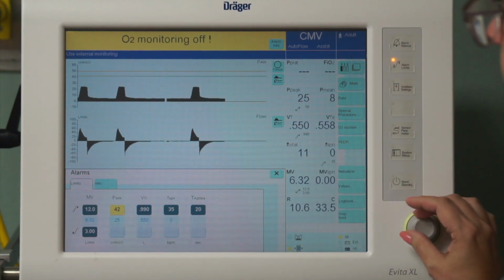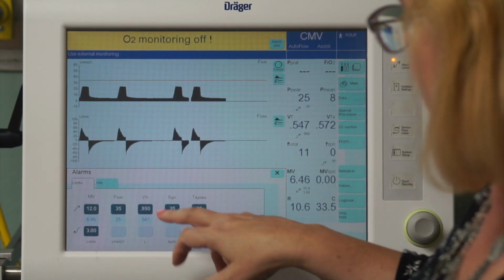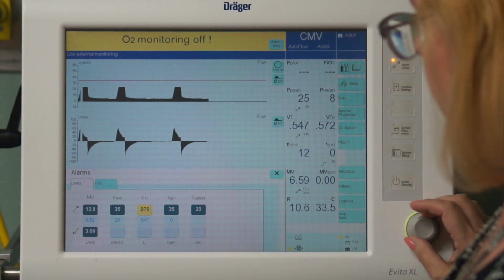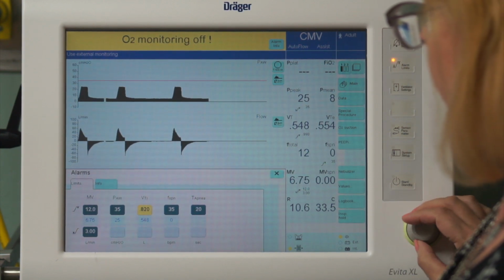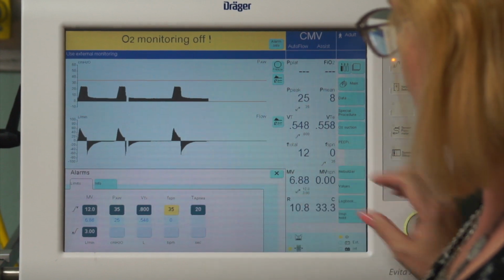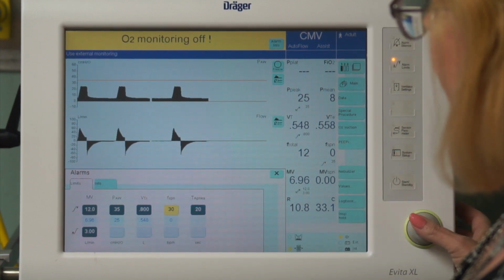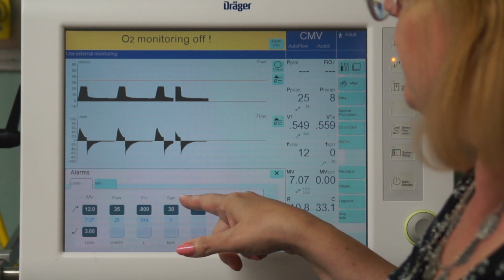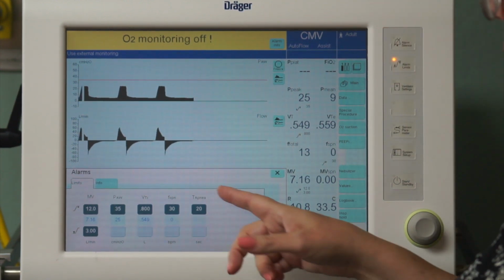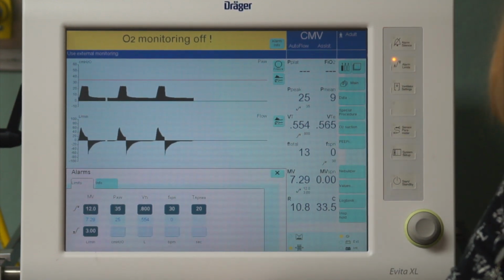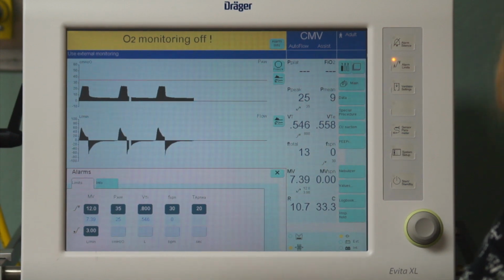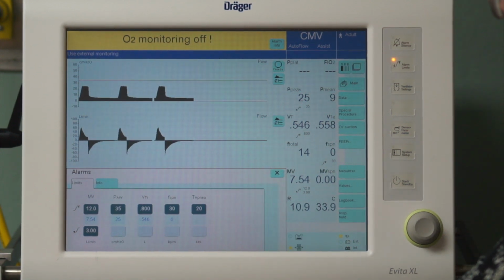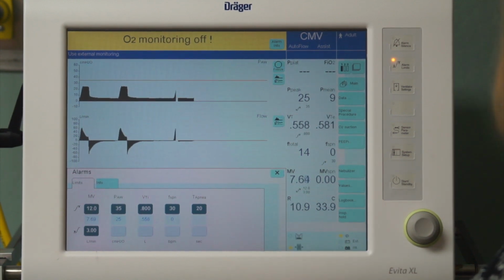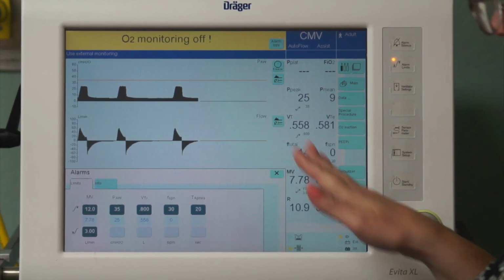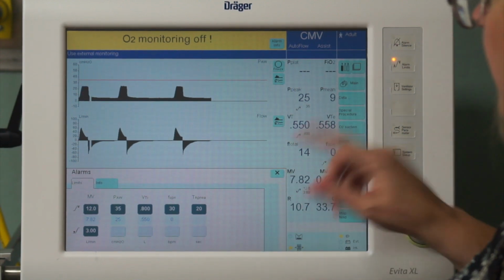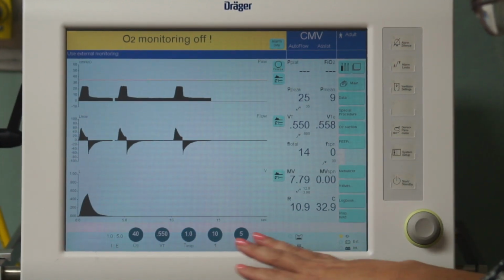Peak pressure, high of 50 seems a little excessive for this patient. High tidal volume. High respiratory rate. And notice what this says. This is a spontaneous respiratory rate. It's not a high machine respiratory rate, because if you think about it, that would be redundant, right? Because it's not going to be too high. So it's going to be our patient's spontaneous respiratory rate and our apnea, right? So we're going to set our 20-second apnea. So those all look good. So I'm going to close that out.